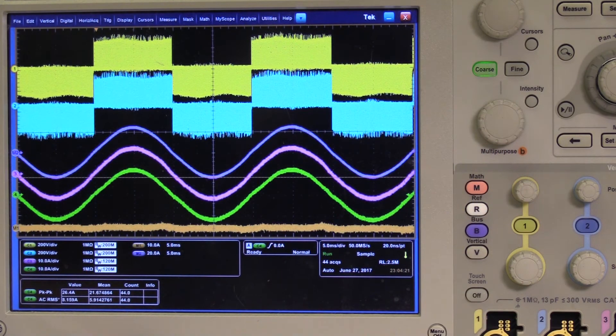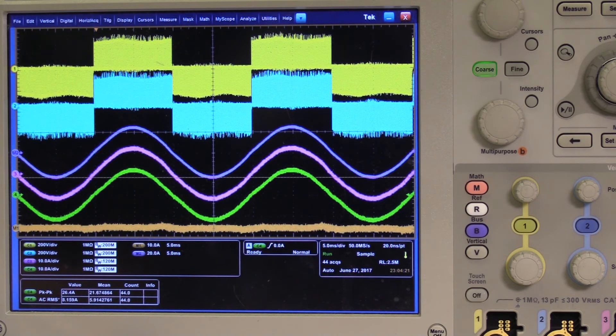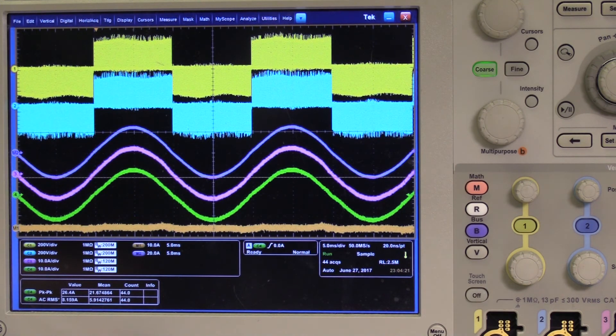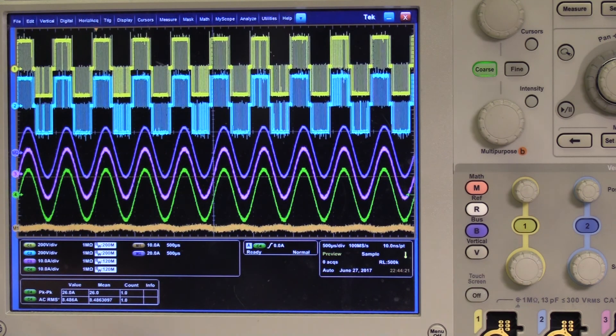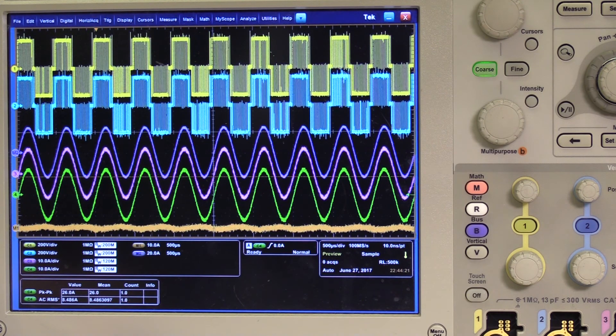These are the waveforms recorded when two modules are working in parallel. This one is at 50 Hz output frequency and 10 kVA output power. From top to bottom, there are phase leg output voltages of the two modules, the total current, the two module currents, and the difference between the two. It is observed that the difference is small, although there is no active control on mitigating it. This is the steady-state waveform under 2 kHz full power operation. No obvious circulating current is observed here.